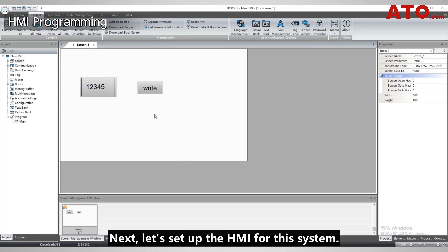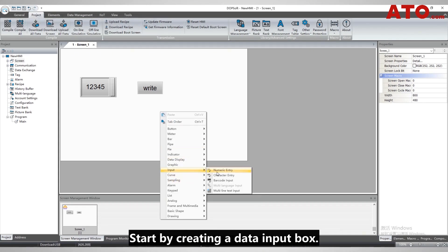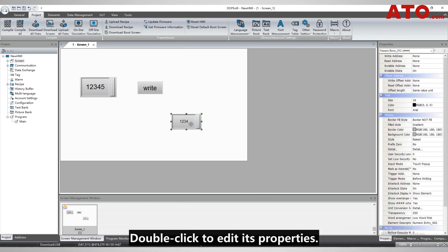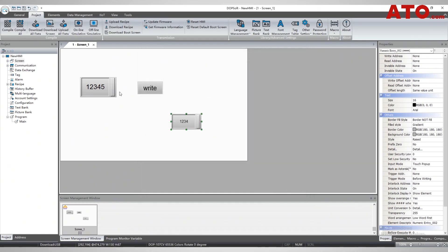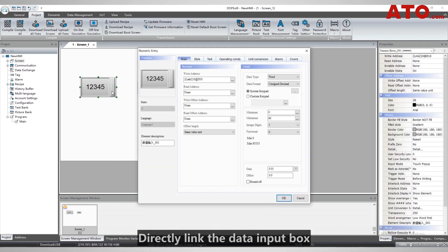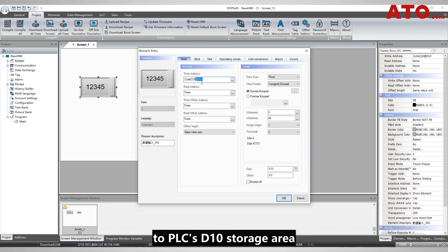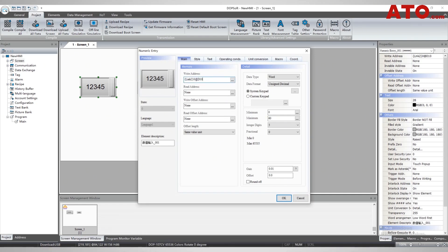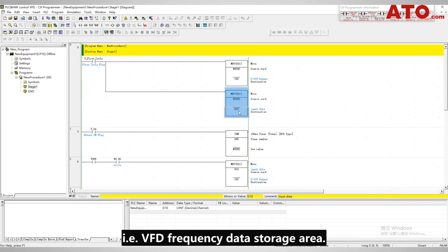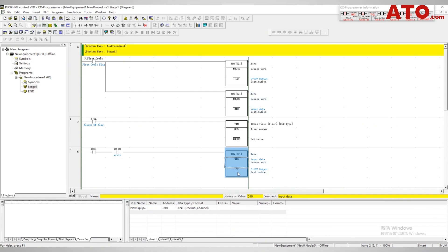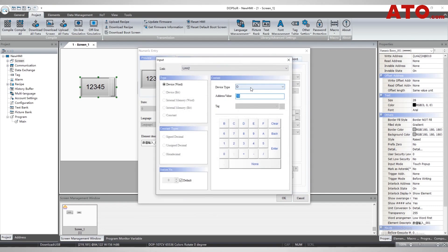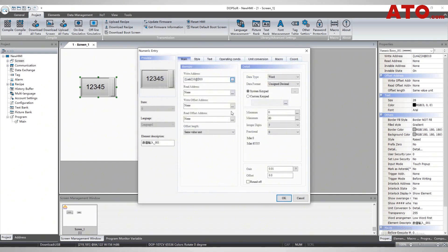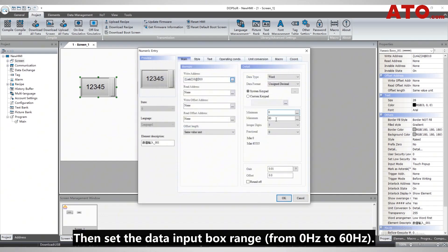Next, let's set up the HMI for this system. Start by creating a data input box. Double-click to edit its properties. Directly link the data input box to the PLC's D10 storage area, which is the VFD frequency data storage area. Then set the data input box range from 0 to 60 Hz.